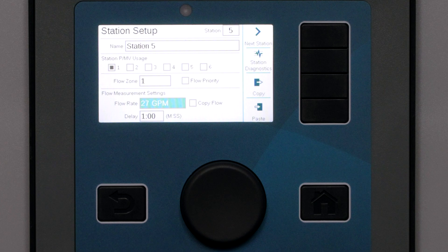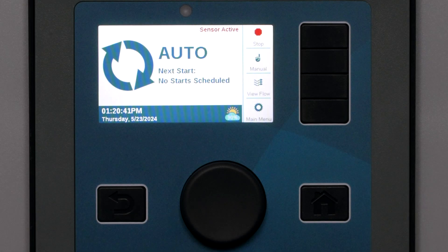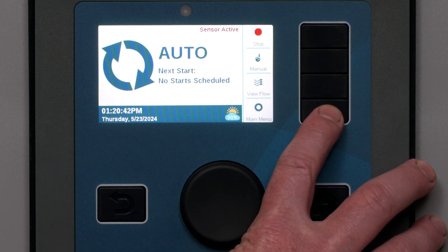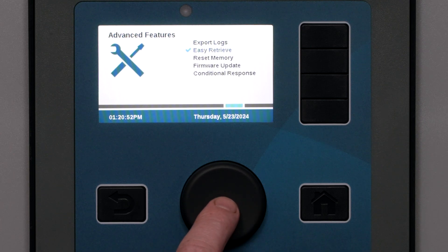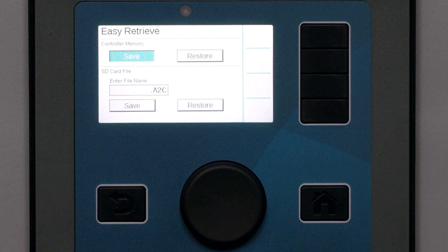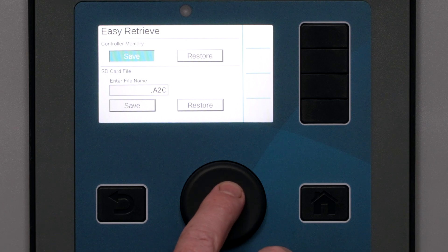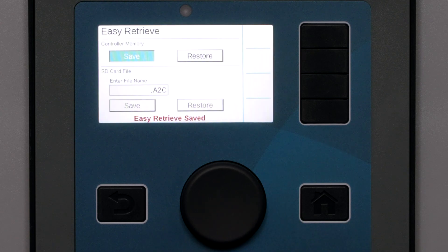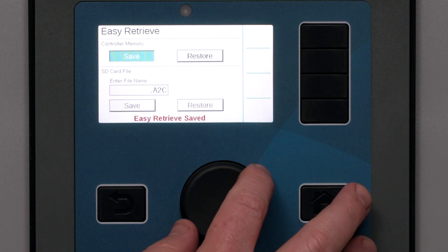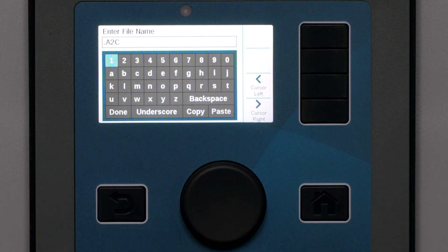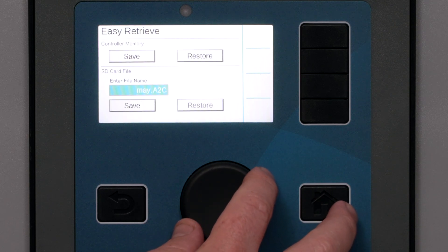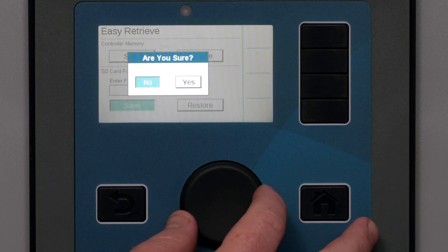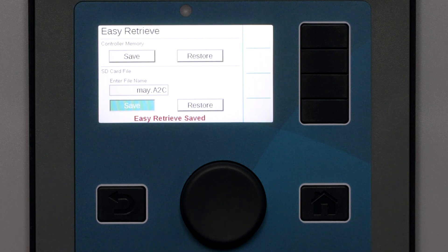After flow learning is complete, the learned flow for each station will be displayed on its page in the station setup screen. You can also enter or edit individual station flows by hand, but learning with an accurate sensor is usually more accurate. You can back up your learn flow progress to the controller's memory or with an external card by going to the Advanced Features menu and selecting Easy Retrieve. You can store a backup in the controller's memory by clicking save, or store it on the controller's SD card with a file name and remove the card for safekeeping. If your face pack is ever replaced, you will always have a backup copy that can be restored with a couple of clicks.